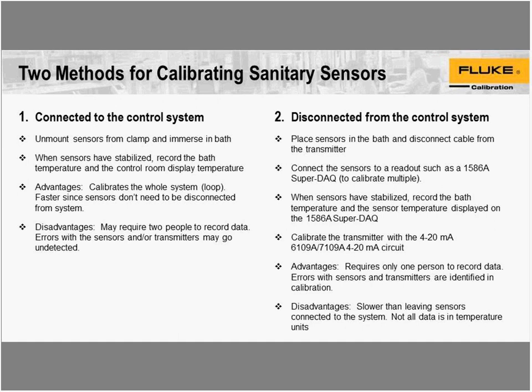The two methods for calibrating sanitary sensors, assuming that these sensors are connected to a typical automation system or control system. In a lot of factories, most of the time this is connected to 4 to 20 milliamp transmitters, maybe connected by means like a PLC or something else. The control system is used to generally describe what provides the measurement and readout of the sanitary sensor.